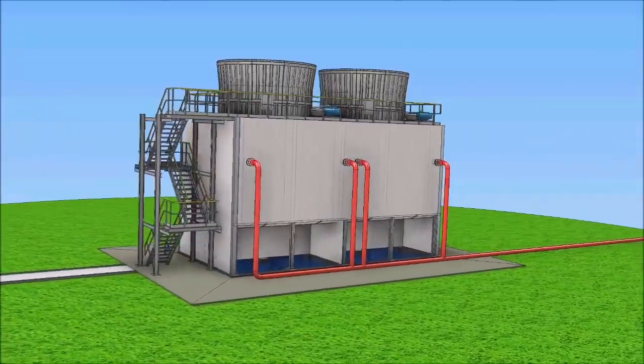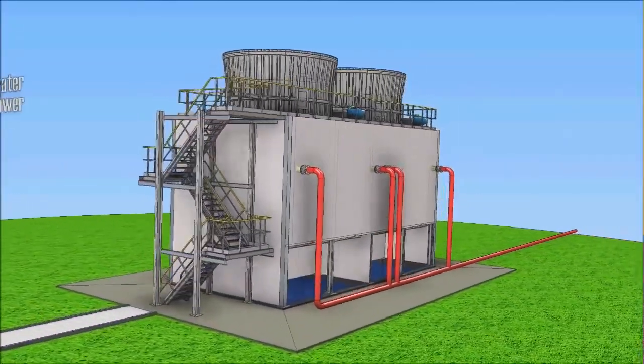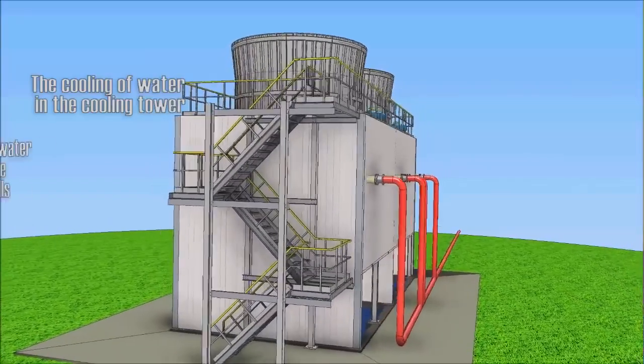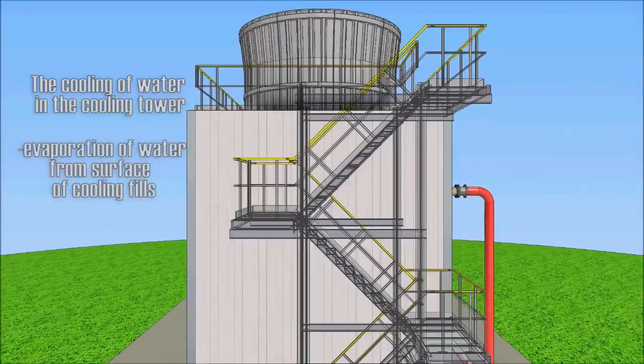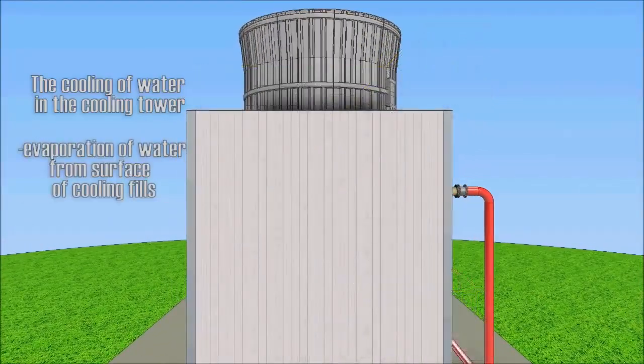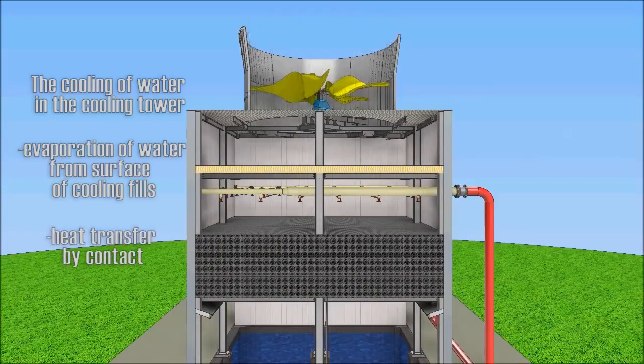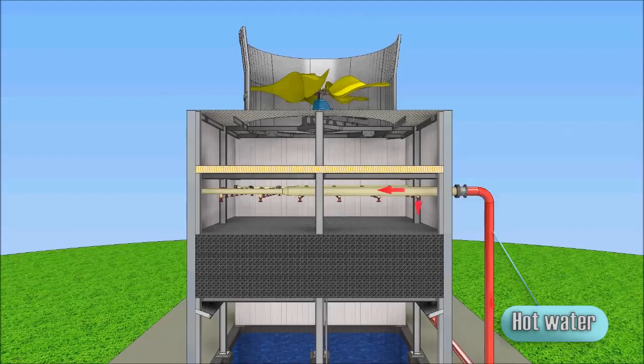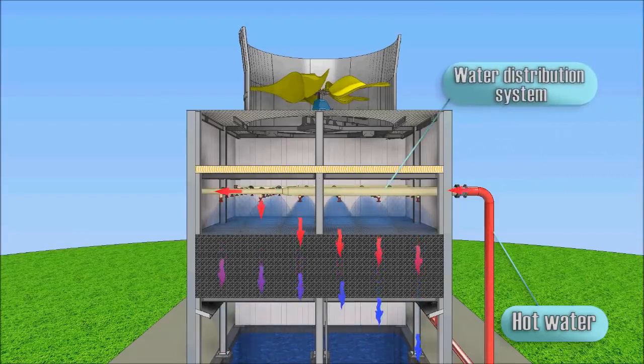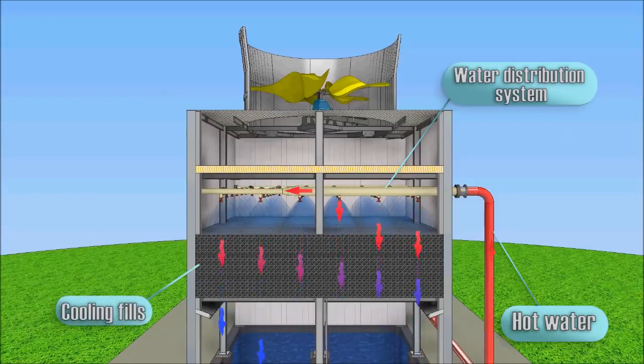So, how is the cooling tower working? Water in cooling towers is cooled by evaporation of water in the stream of atmospheric air through heat transfer by contact with air. Hot water from various sources such as machines or heating processes flows through pipes to the distribution system of the cooling tower, which produces even water distribution to all the area of fills by spray nozzles.